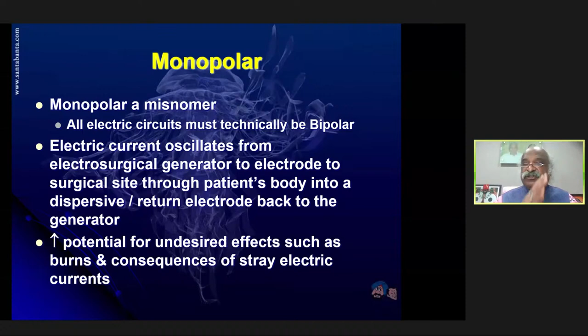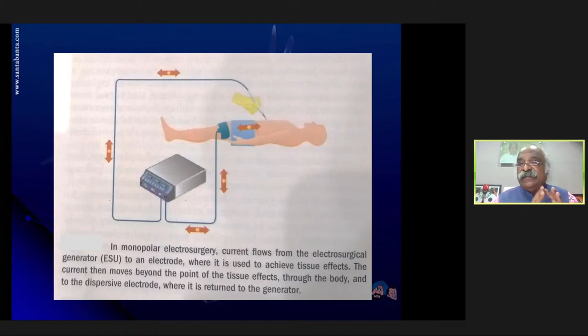And that complete circuit is why it is a misnomer; technically, it is bipolar. In monopolar electrosurgery, current flows from the electrosurgical generator to an electrode, which touches the body at the site to achieve the desired tissue effects. Then the current moves to the dispersive electrode, enters it, and goes back into the electrosurgical device. This way the circuit is completed, and that is the principle of what we call monopolar. Because this name was there, we are using it.